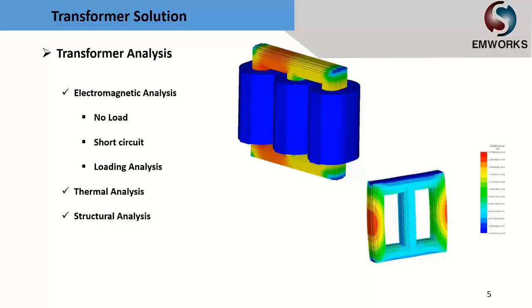We also have thermal analysis. When a transformer is loaded, it is not ideal — there is resistance in the coil and core losses in the steel core, which generate heat. We need to understand how much the transformer will heat up in order to design a proper cooling system. Finally, we have structural analysis, which is important for special conditions — for example, when a short circuit occurs and high current creates a strong magnetic field that produces strong forces, potentially causing deformation of the core.